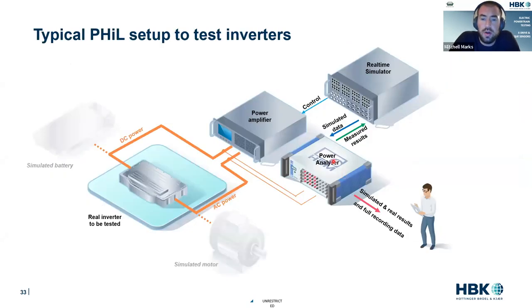On the same note, we can also test power hardware in the loop for, let's say, an inverter, where you measure a physical inverter and you have a simulated battery and motor. We have communication profiles with real-time simulators. We make the measurements on things like an inverter, and we do enable hardware in the loop because we offer that real-time feedback to things like the real-time simulator. We can act as a power front end. I won't belabor this. It's the exact same as system integration. We can receive commands. We can share data.